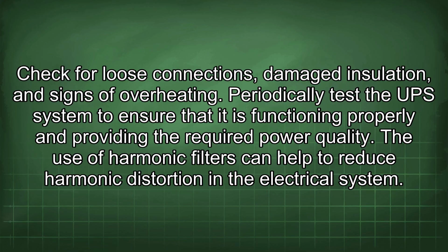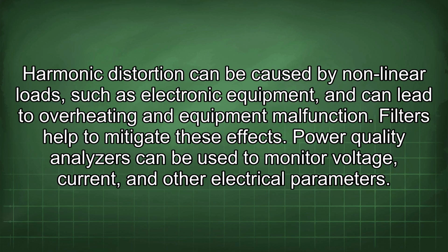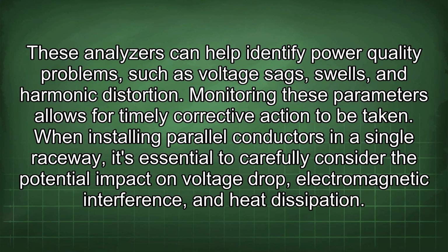The use of harmonic filters can help to reduce harmonic distortion in the electrical system. Harmonic distortion can be caused by nonlinear loads, such as electronic equipment, and can lead to overheating and equipment malfunction. Filters help to mitigate these effects. Power quality analyzers can be used to monitor voltage, current, and other electrical parameters. These analyzers can help identify power quality problems, such as voltage sags, swells, and harmonic distortion. Monitoring these parameters allows for timely corrective action to be taken.